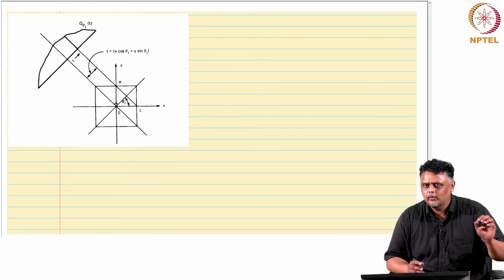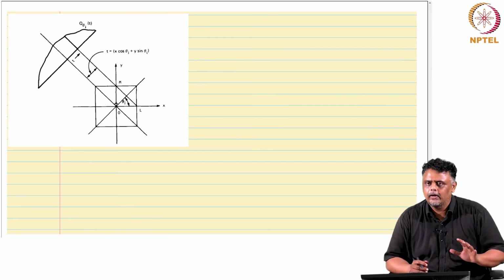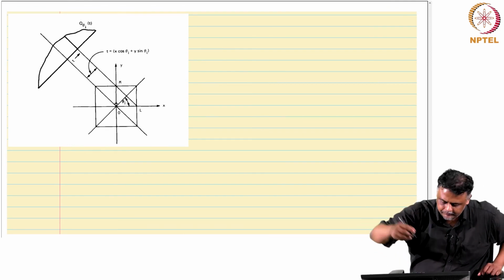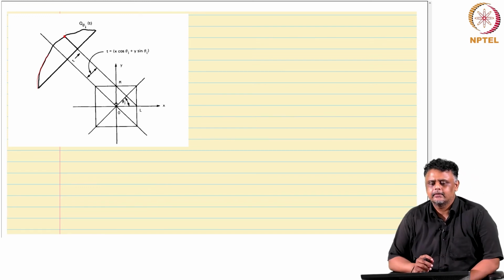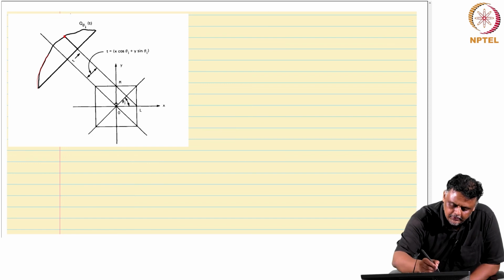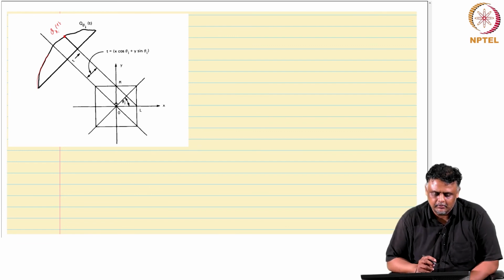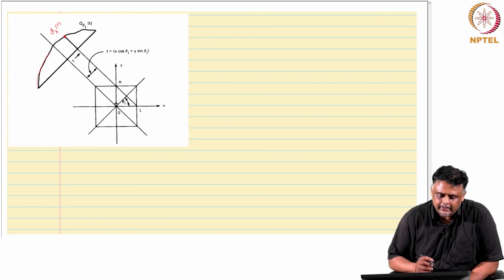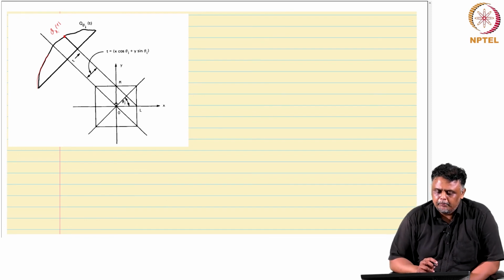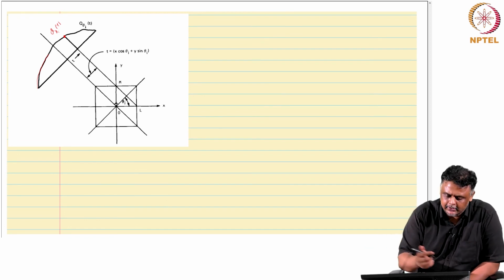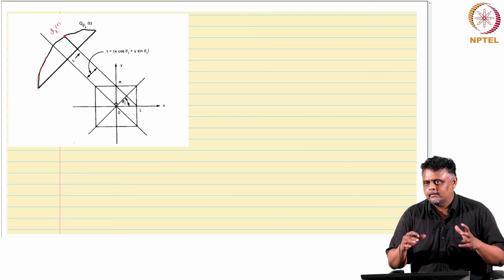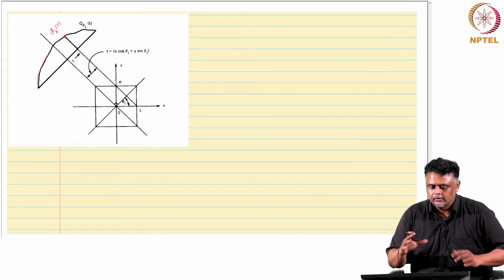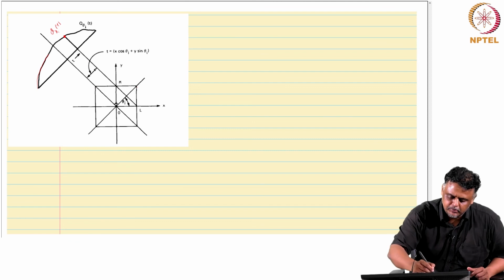So, how do you reconstruct? Very quickly, I am not going to walk through the specifics. A very simple way of looking at it: this is the projection data right there. You take a point in the projection, some value it has, in this case indicated by q theta i of t. I apologize, all my theta and q look the same. You take this point, but I will do the pre-processing later, I will just tell you how the reconstruction is done. Then you construct the grid. This box you see here is the image array or grid that you define, it is a digital array, and you take this point and smear it across the grid.